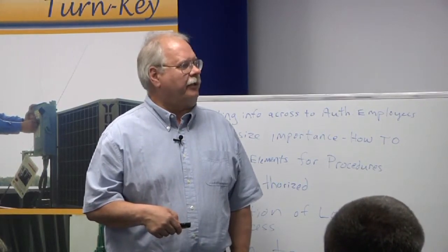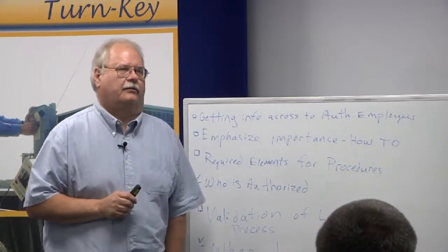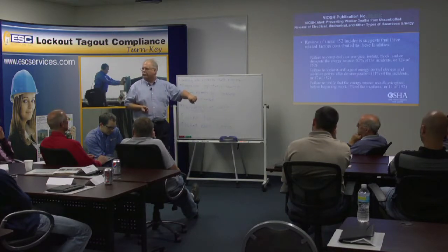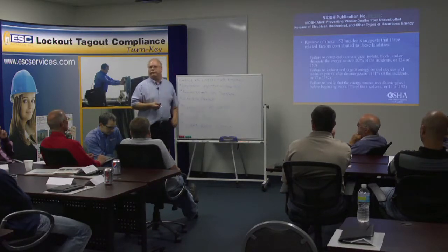Failure to verify that the energy source was de-energized before beginning work is another major cause. I pull the disconnect out and assume it's off without going back with my meter. What happens? It has the potential to still be on. I've had failures — I've had arms down, switch still in, blades still in because nobody maintained them. They kind of welded themselves in when somebody had to use a pry bar to bring it down and broke the old plastic.